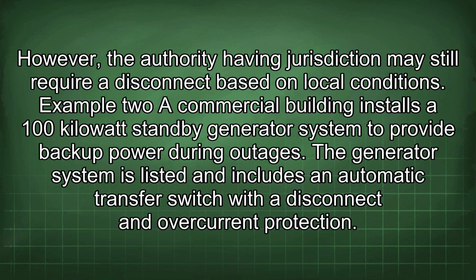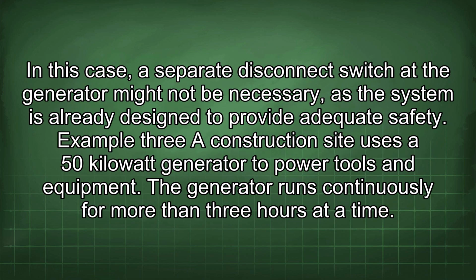Example 2. A commercial building installs a 100 kilowatt standby generator system to provide backup power during outages. The generator system is listed and includes an automatic transfer switch with a disconnect and overcurrent protection. In this case, a separate disconnect switch at the generator might not be necessary, as the system is already designed to provide adequate safety.